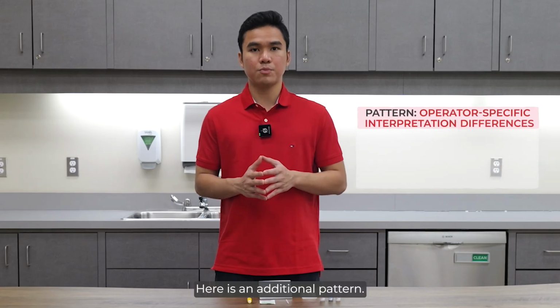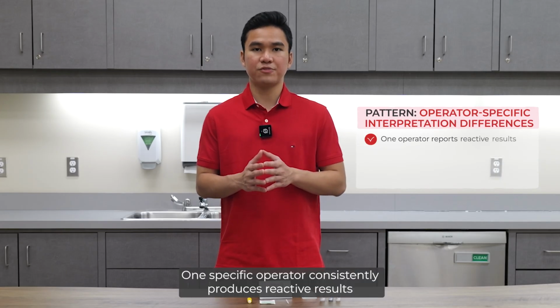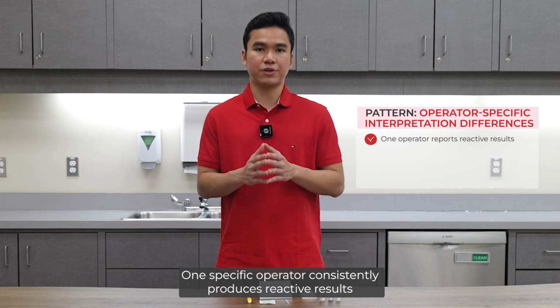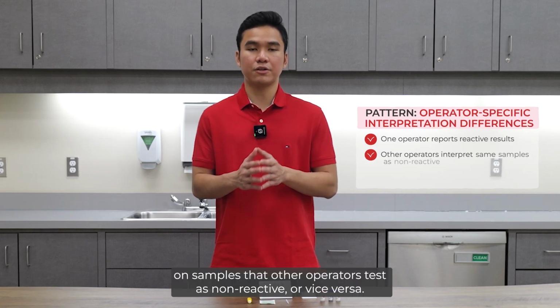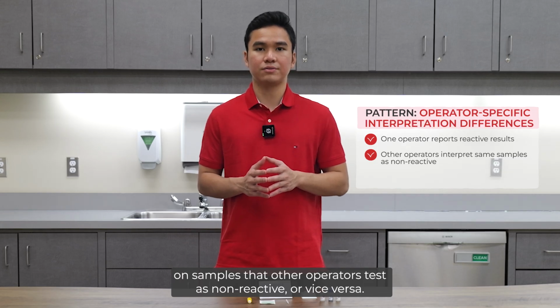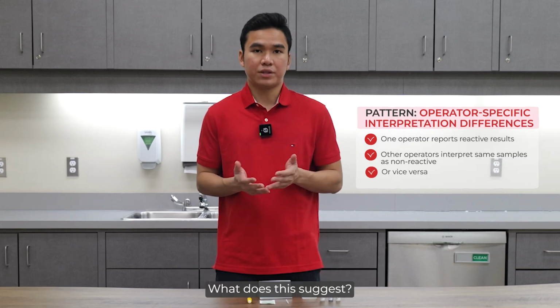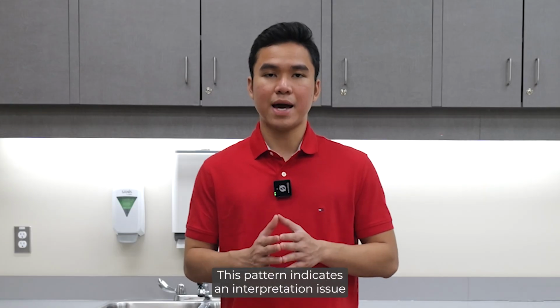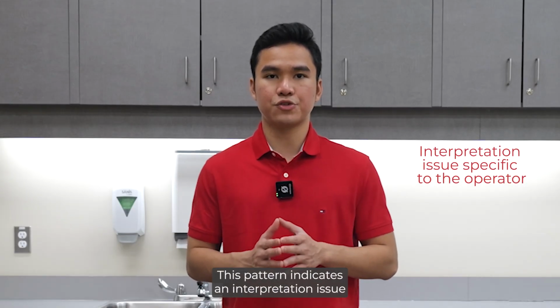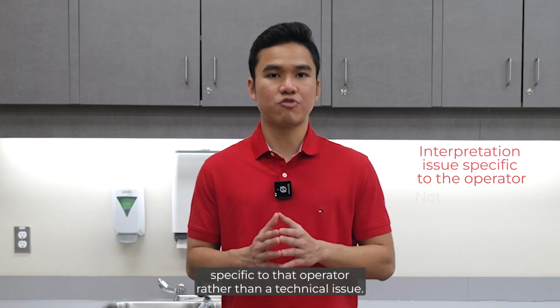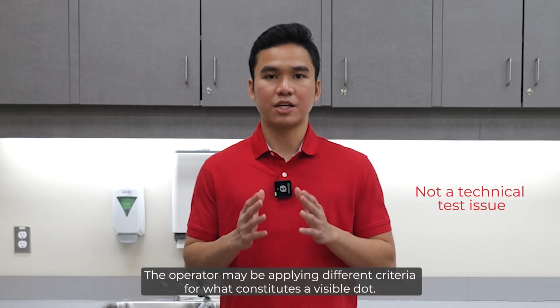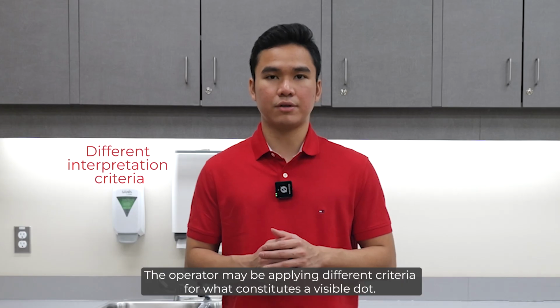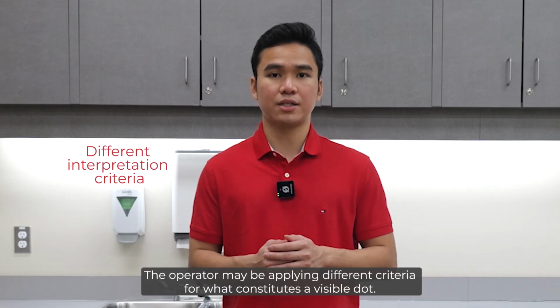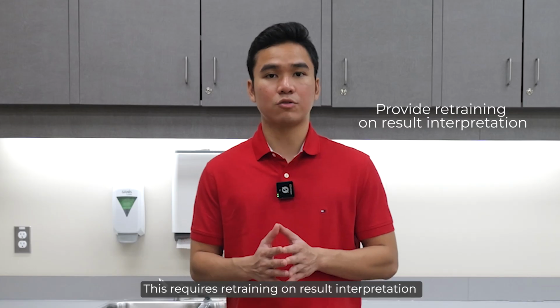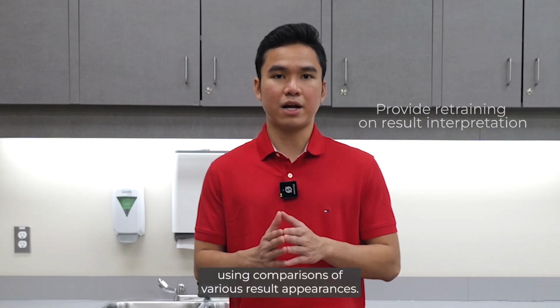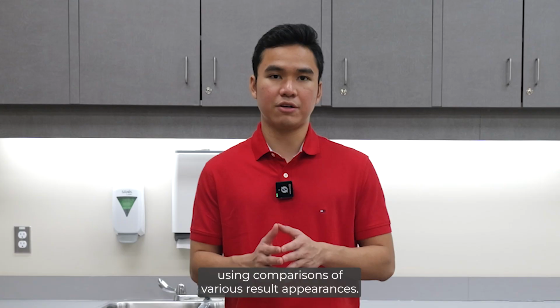Here is an additional pattern. One specific operator consistently produces reactive results on samples that other operators test as non-reactive, or vice versa. What does this suggest? This pattern indicates an interpretation issue specific to that operator rather than a technical issue. The operator may be applying different criteria for what constitutes a visible dot. This requires retraining on results interpretation using comparisons of various result appearances.